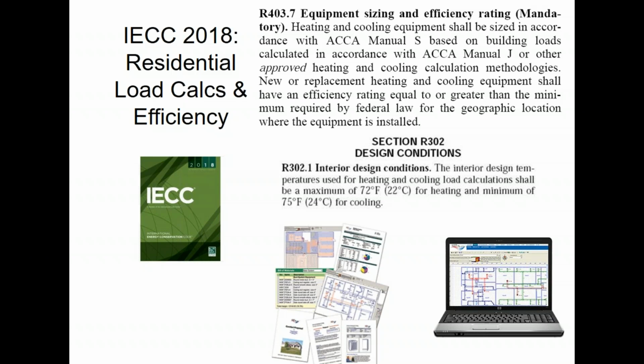So if you somehow do a good load calc and stop oversizing, all of a sudden a higher temperature is going to be more comfortable for people because it'll be dehumidified better. So in my house, we keep it at 77 or 78 degrees. Not because we like it warm or anything like that, just because it's ultra dry in my house in the summer, 30s and 40%, whereas everybody else's house around in my neighborhood is in the 60s and 70%. So they have to have a really cold temperature in order to drive their humidity down.